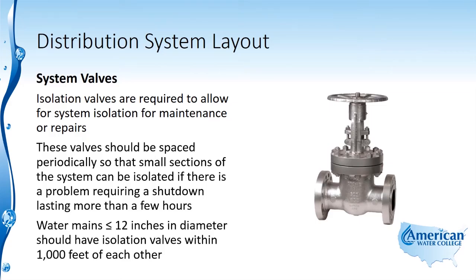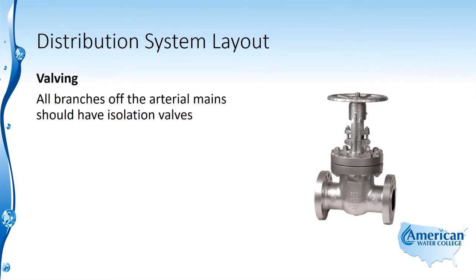Water mains less than or equal to 12 inches in diameter should have isolation valves within 1,000 feet of each other. All branches off the arterial mains should have isolation valves as well.